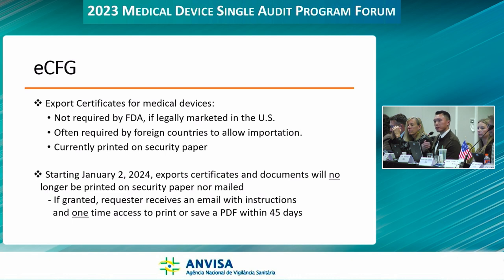Again, ECFG, it's the electronic certificates for medical devices. It's not required by FDA if legally marketed in the US, but it's often required by foreign countries that don't have an established regulatory scheme or structure. So it allows us to certify that these products meet QSR GMP requirements.